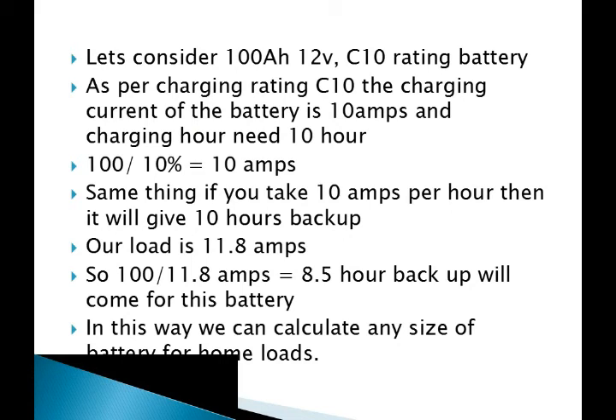Let us consider a 100Ah, 12V, C10 rating tubular battery. As per the C10 charge rating, the charge or discharge current is 10% of the battery capacity. That means 100Ah multiplied by 10% equals 10 amperes. So this battery provides a 10-hour backup when discharging at 10 amperes.